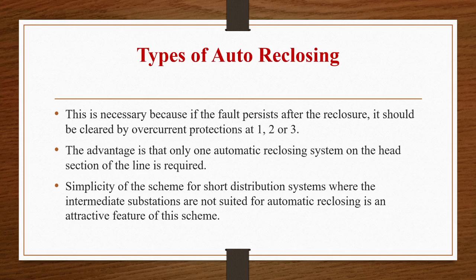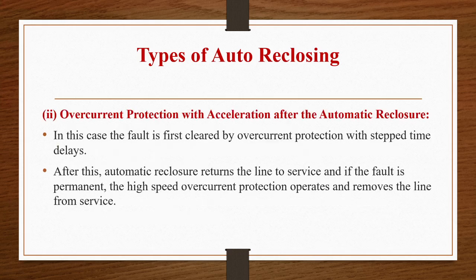Now, the simplicity of the scheme for short distribution systems where the intermediate substations are not suited for automatic reclosing is an attractive feature of this scheme. So, what is the simplicity of the scheme? That for short distribution systems where intermediate substations are not suited for automatic reclosing is an attractive feature of this scheme. Now, let us see the second one, overcurrent protection with acceleration after the automatic reclosure.